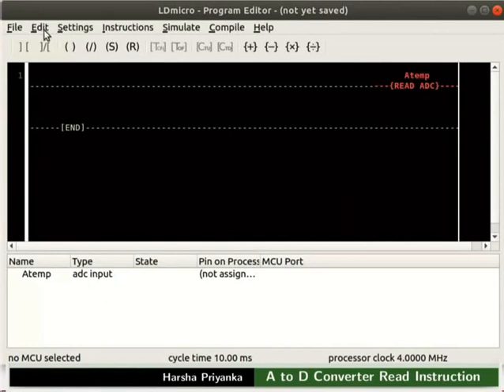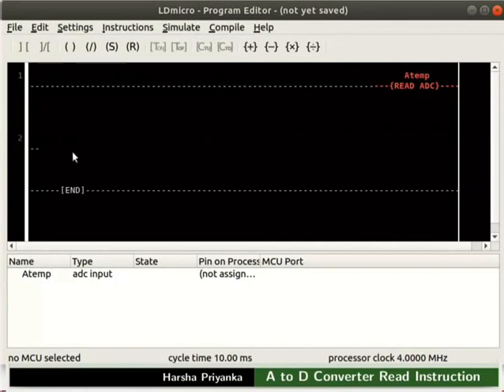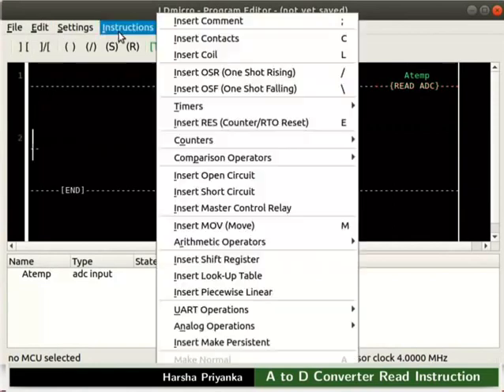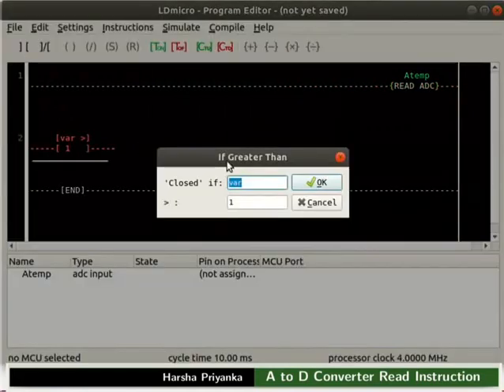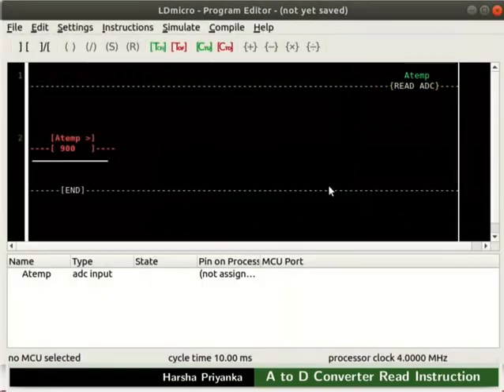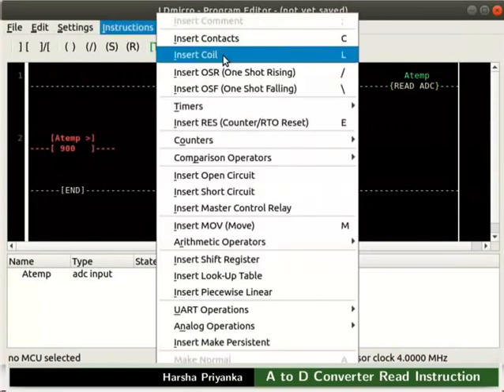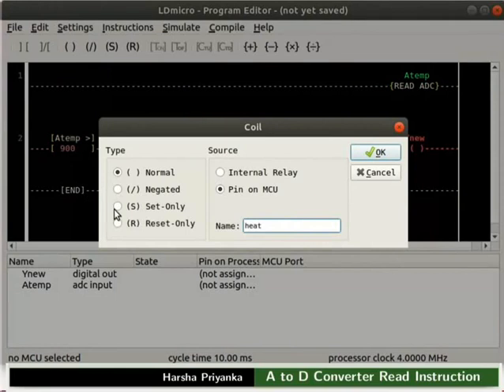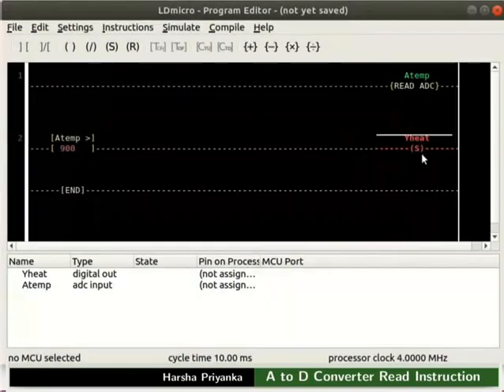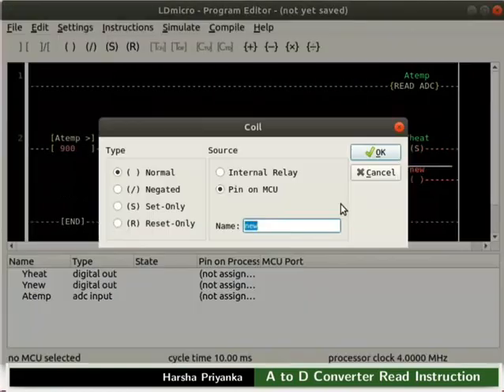Now, insert a rung below. Insert a greater than compare instruction in the new rung as shown. Double click on it. Set the variable to ATemp and compare it to 900. Click the OK button. To the right of it, insert a coil. Rename the coil as heat and configure it as SetOnlyCoil. Now, parallel to Y heat, insert another coil. Rename it as new and configure it as ResetOnlyCoil.